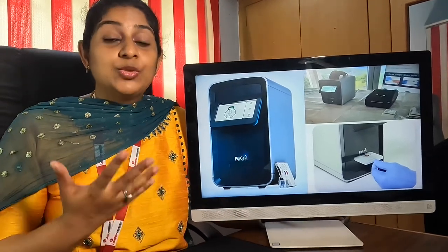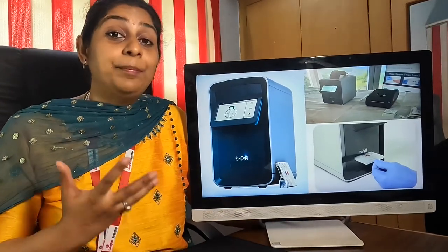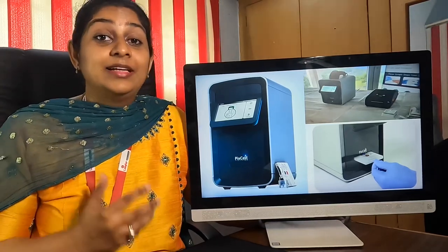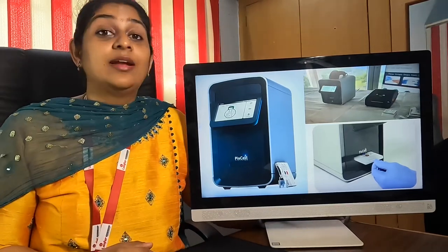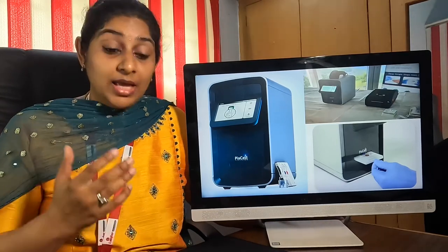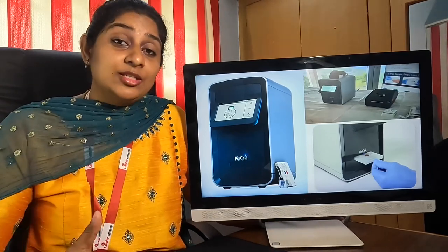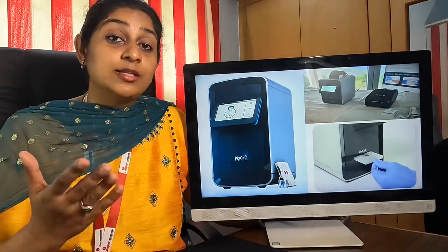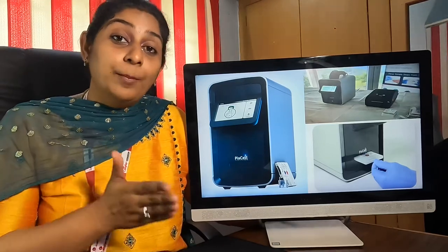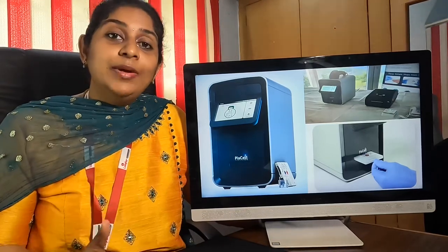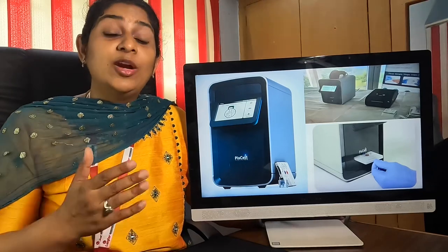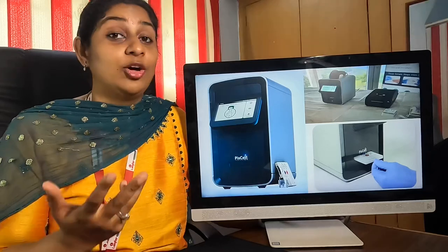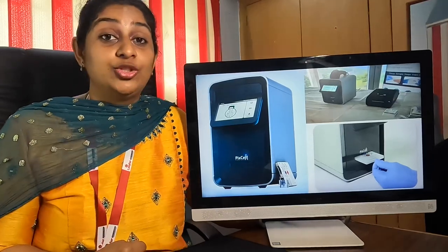The fourth point you need to see while choosing your hematology analyzer is the parameters. Three part parameters are different, five part parameters are different, and a six to seven part hematology analyzer gives different additional parameters. It is not the number of parameters you get, but the type of parameters that is most important. You need to note what are the measured parameters, how many are the calculated parameters, and what are the other research or new parameters which are an add-on in your hematology analyzer.